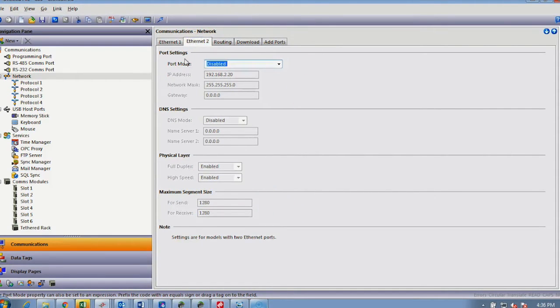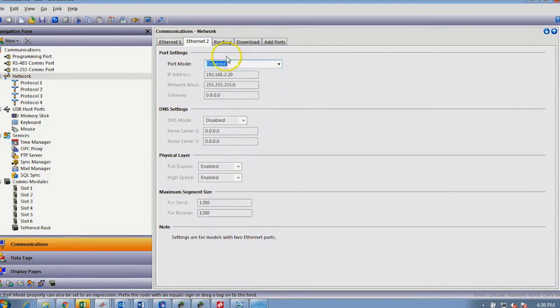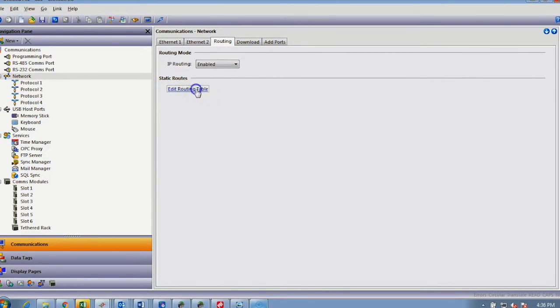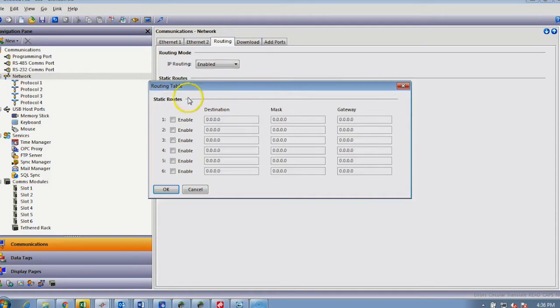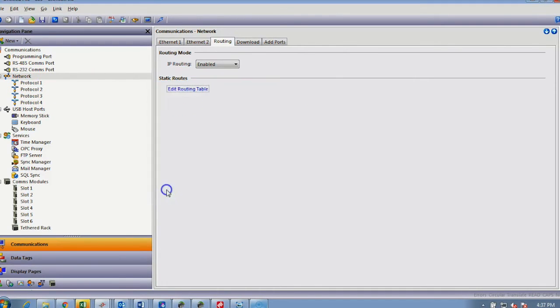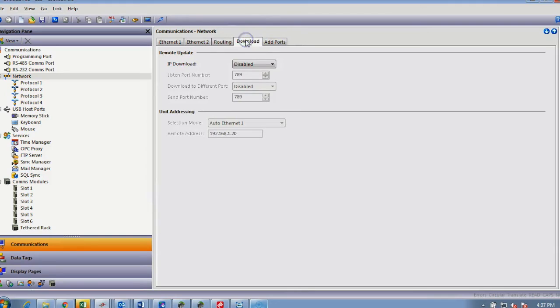The second Ethernet port can be configured exactly the same as Ethernet one. And of course, once you have two Ethernets in play, you can route between both networks to some of the end-connected devices simply by enabling and putting the destination gateways in place between the devices that are connected. Of course, you can download via the IP, but you have the option of not enabling this and locking the device down from this aspect.